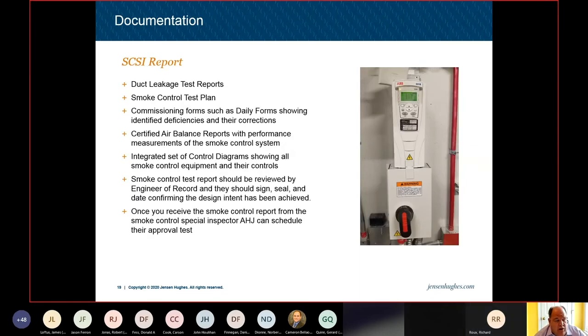So as part of the smoke control special inspector's role for this new construction job, they've been involved through the duration of the project. During construction, they've been in the field doing rough inspections. They developed a smoke test plan to tell everyone how they're going to test this smoke control system. They've reviewed submittals and cut sheets to make sure all the pieces and parts fit. That includes the fire alarm pieces that are interacting and interfacing with the smoke control system. That includes some smoke control requirements for the fans. It includes sprinkler system reviews. It includes a lot of different things to coordinate the integration of those various systems, which eventually lead up to testing, right?